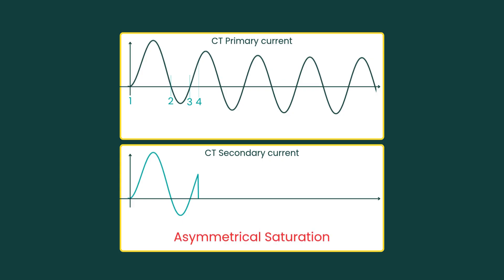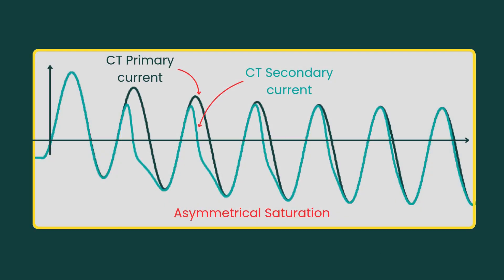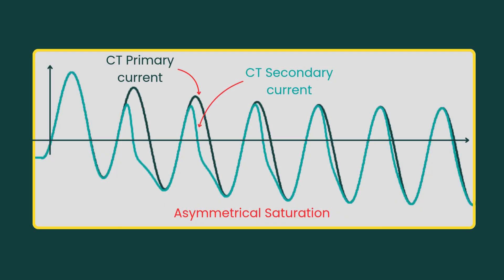It's not just the fault current magnitude that causes it; the DC offset plays a key role, especially during the first few cycles. For protection relays, this matters a lot. They rely on the CT's output during transient conditions to operate correctly.